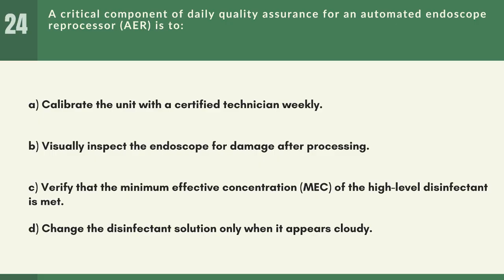Question 24. A critical component of daily quality assurance for an automated endoscope reprocessor, AER, is to A. Calibrate the unit with a certified technician weekly. B. Visually inspect the endoscope for damage after processing. C. Verify that the minimum effective concentration, MEC, of the high-level disinfectant is met. D. Change the disinfectant solution only when it appears cloudy.